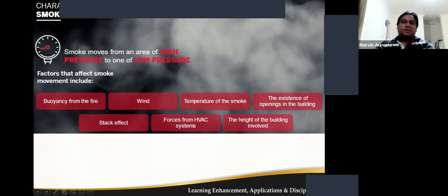The smoke moves from areas of high pressure to low pressure, and a pressure difference from one space to another may be caused by buoyancy from the fire, stack effect, wind and forces from the building, and the HVAC system.